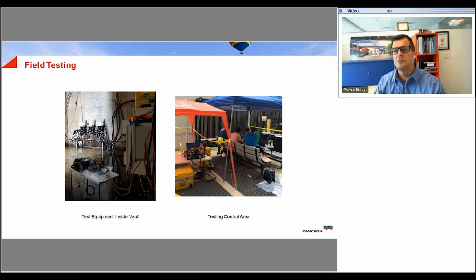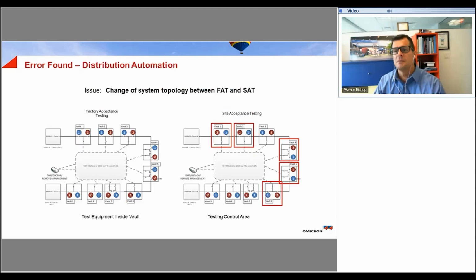One of the major hurdles which presented itself, an issue that we actually found with the system that we would not have otherwise found using the traditional testing method or just individual relay testing, was the difference of topology between the first lab test versus the site test, where it was actually installed. Due to the physical limitations of some of the rooms where each of the switching devices was housed, the directionality of some of the switches had to be reversed. We see that in the cases of, they refer to them as vaults, vault 1, 2, 4, 5, and 6.